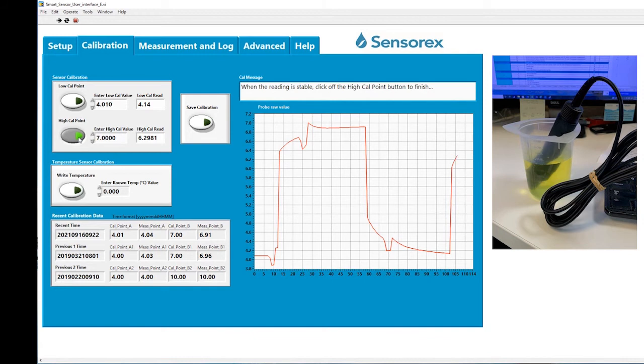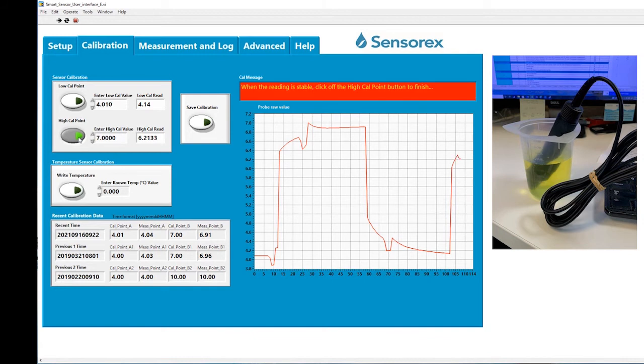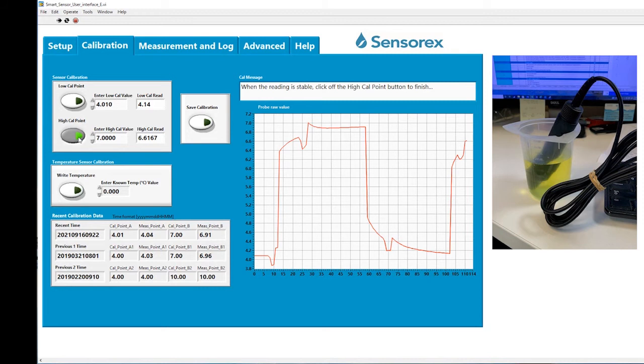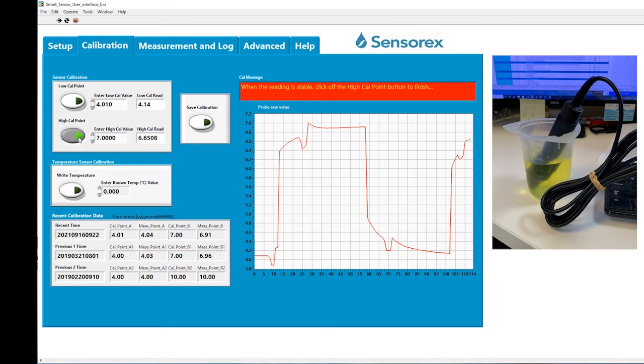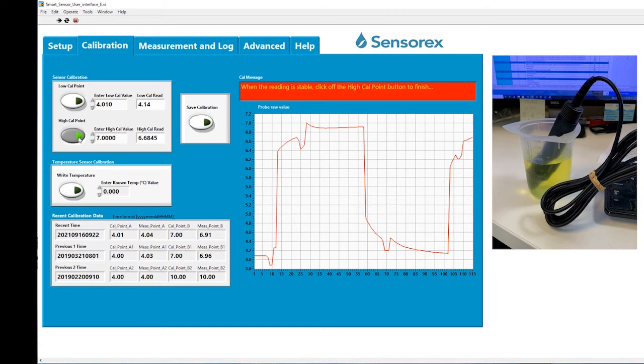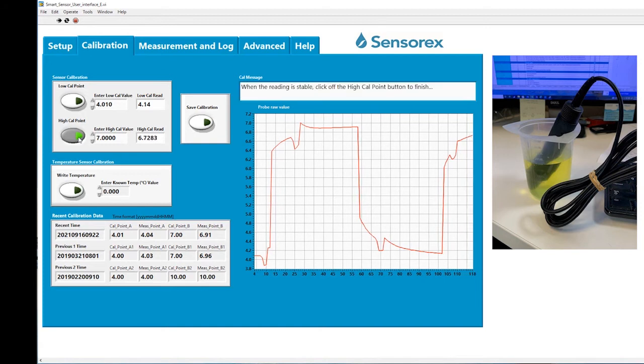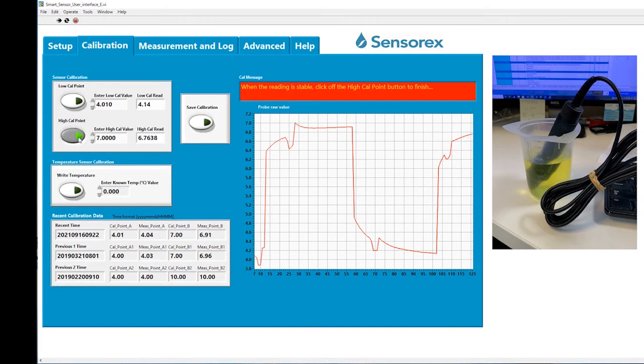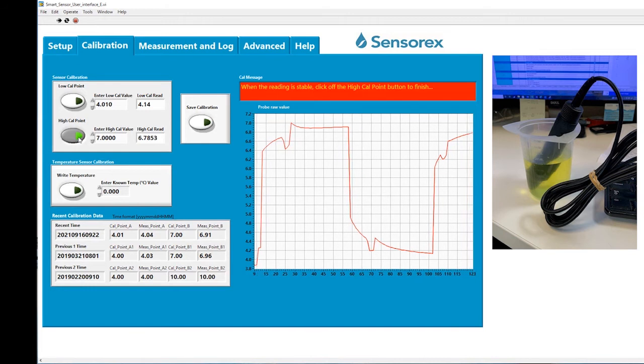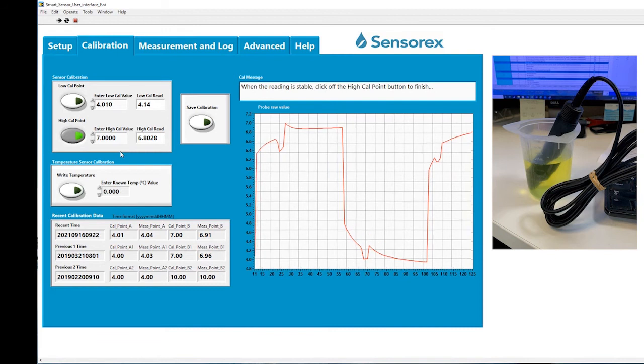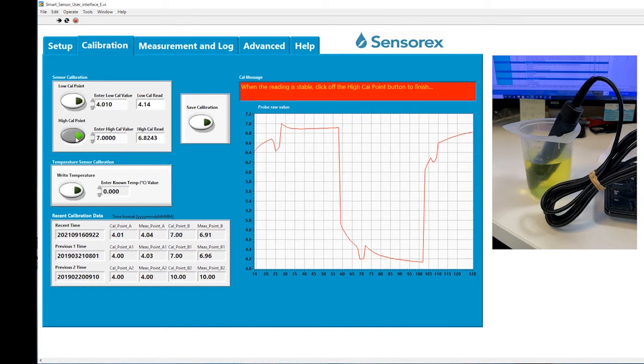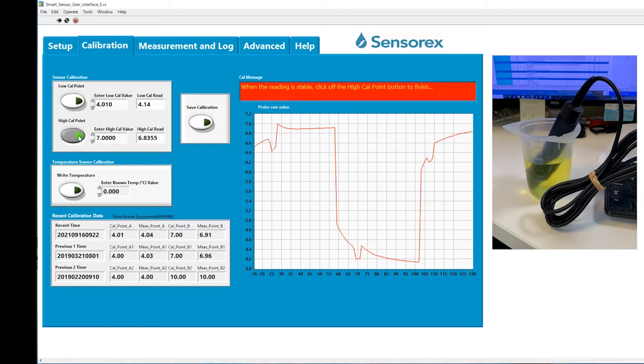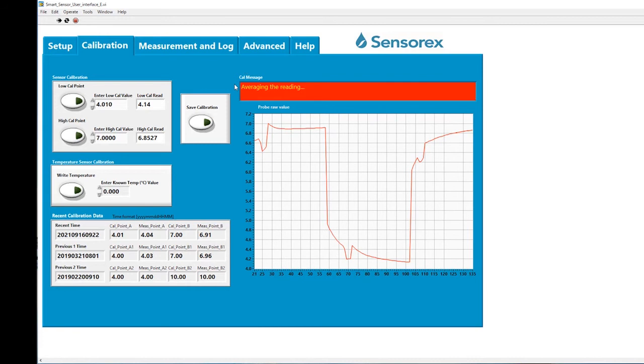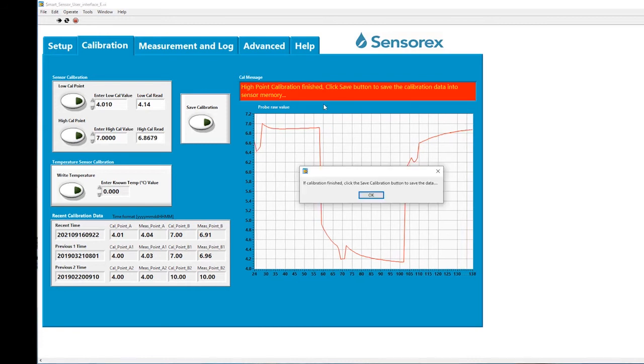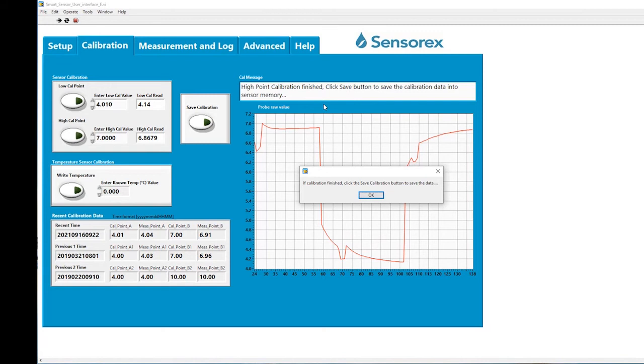We'll just stir the probe again, and get it used to that buffer. Once we see a stable value, again, we will press the high calibration point button, follow our message prompts, and then get a calibration result. We're very close to a stable value, so I'm going to go ahead and just press the button. You'll see again the readings being averaged, and then that the high calibration point is finished.